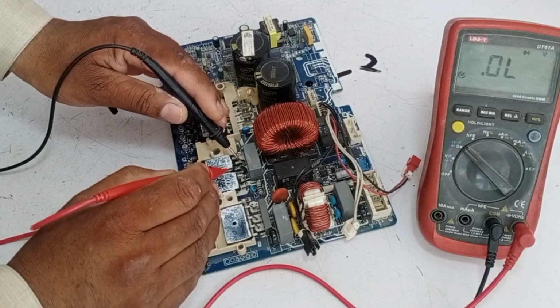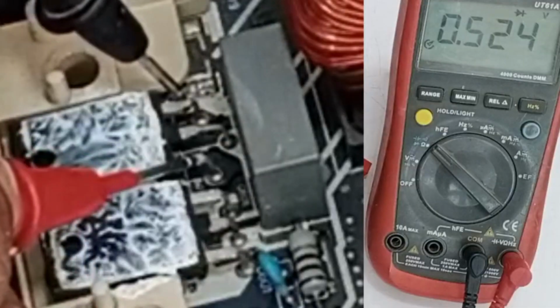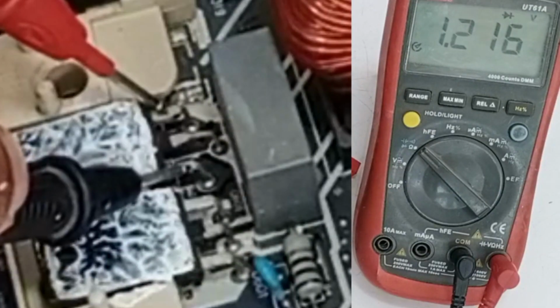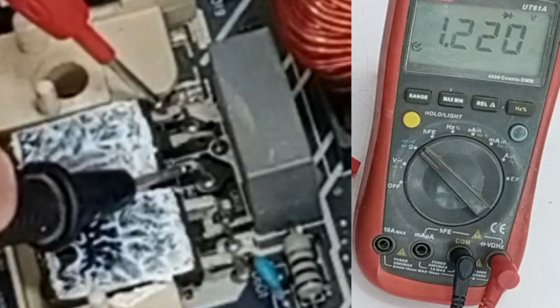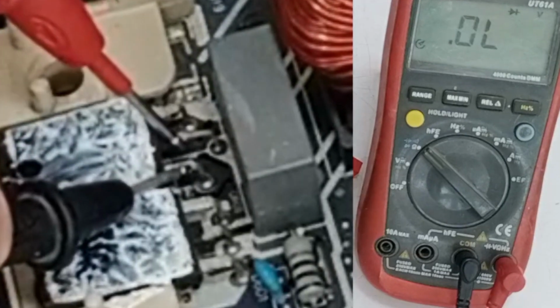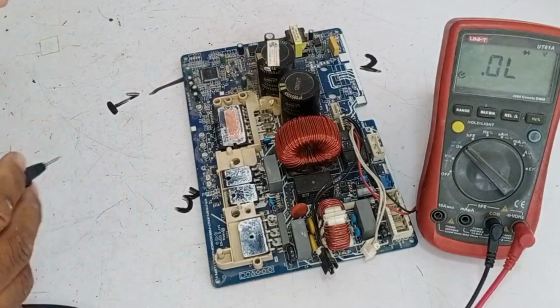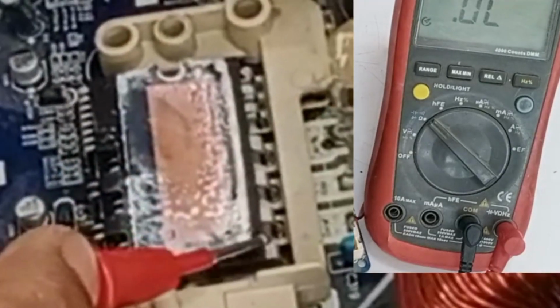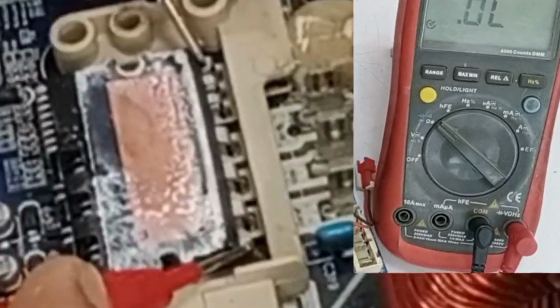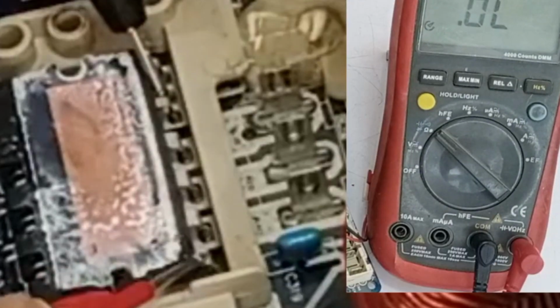Now, after this, let's check the IGBT. We should see the voltage drop on these pins. One point, 220 voltage drop is shown on this pin, which is fine. Now let's move on to check the IPM. First, let's check the positive and negative by placing the positive probe on the positive and the negative probe on the negative and see what it shows.